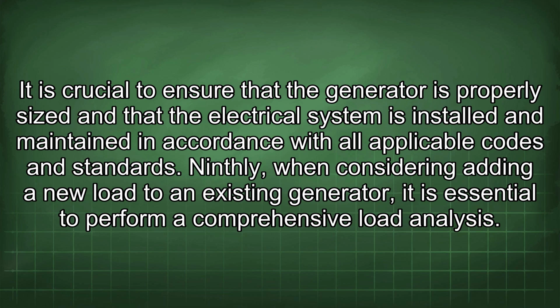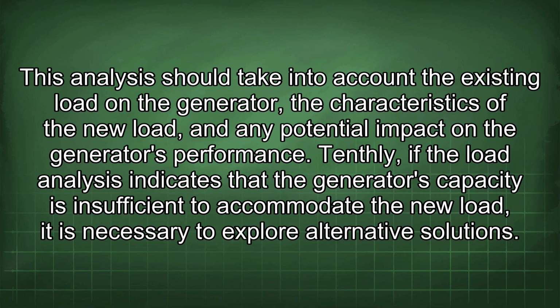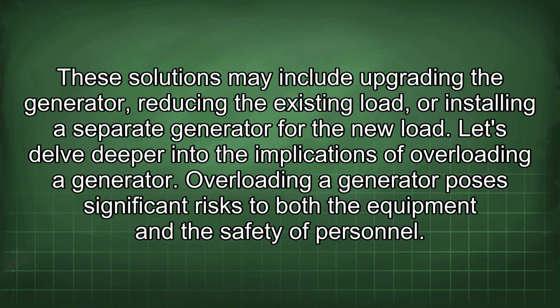Ninthly, when considering adding a new load to an existing generator, it is essential to perform a comprehensive load analysis. This analysis should take into account the existing load on the generator, the characteristics of the new load, and any potential impact on the generator's performance. Tenthly, if the load analysis indicates that the generator's capacity is insufficient to accommodate the new load, it is necessary to explore alternative solutions. These solutions may include upgrading the generator, reducing the existing load, or installing a separate generator for the new load. Let's delve deeper into the implications of overloading a generator.